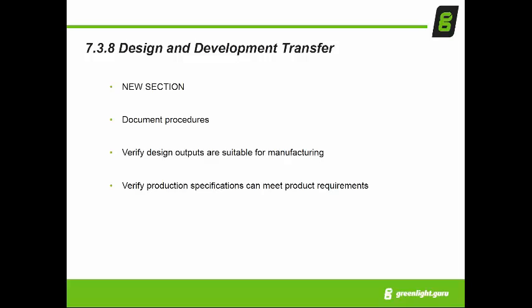You need to make sure those design outputs, I mentioned those design and development outputs being the recipe for your device. The other thing you should think about from design and development outputs is that's your preliminary device master record, which the clause in ISO 13485 calls the medical device file. I'm not touching on that today, but that's in section 4.2.3 of ISO 13485.